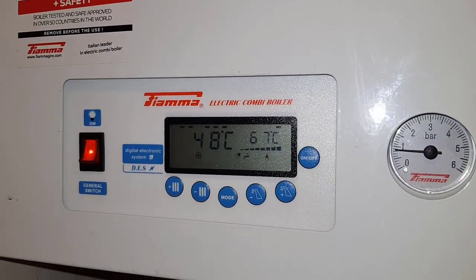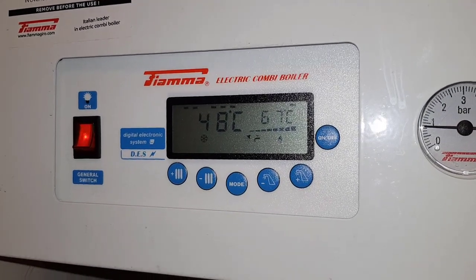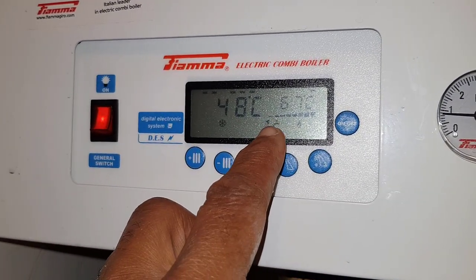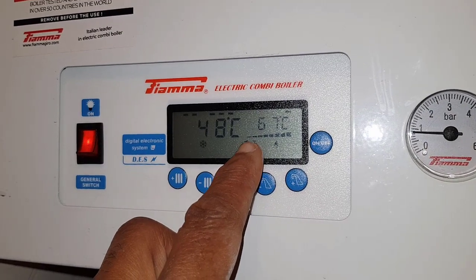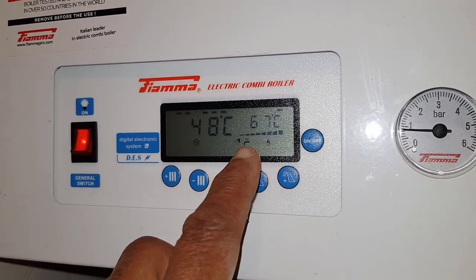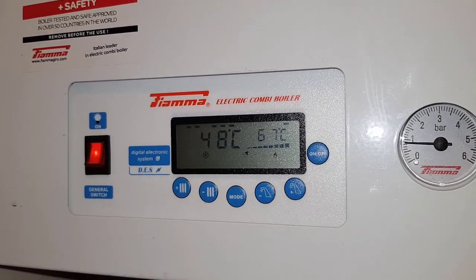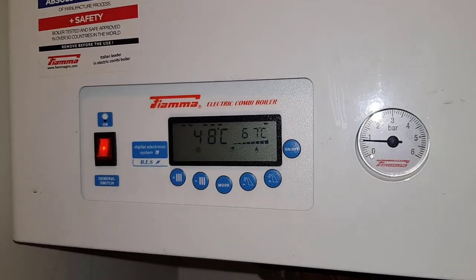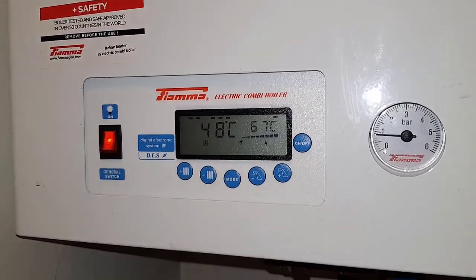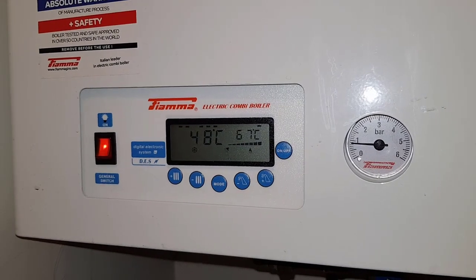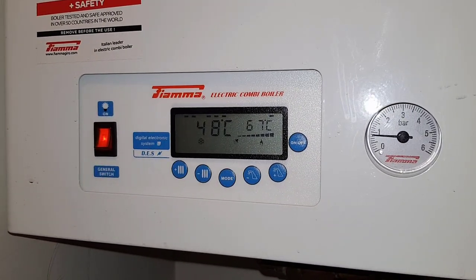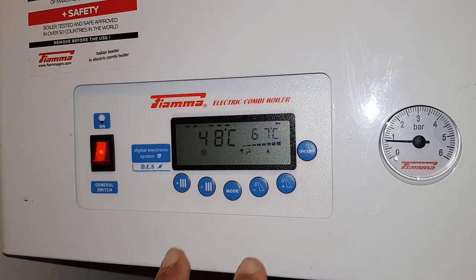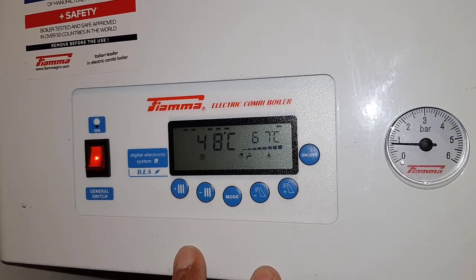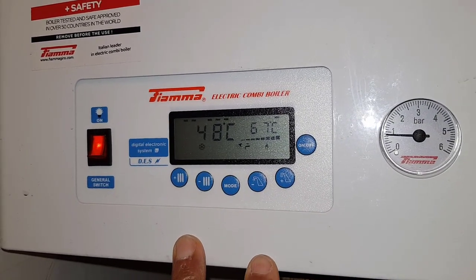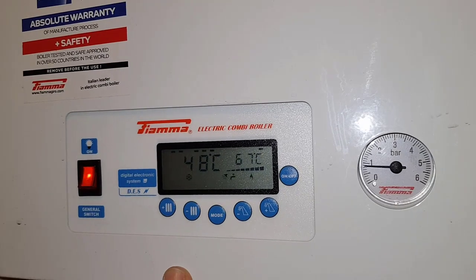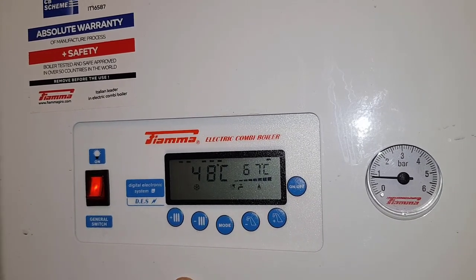But we've had a development. The pump is now running, because when that tap symbol's flashing and that bar goes across, that's what we were expecting before when we ran the hot tap. This is also going back to it not turning off. I said earlier, this is what it's doing. It's running all the time and then going round the heating, because at the moment the hot water tap is not calling.